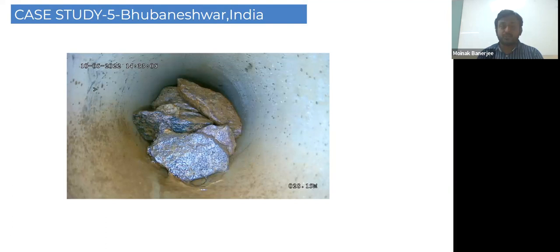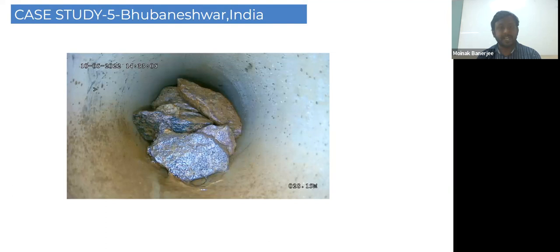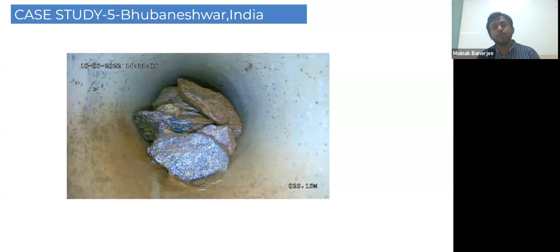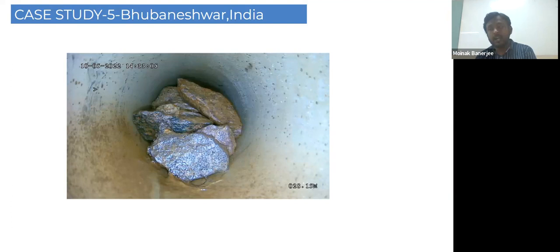Another case study is from Bhubaneswar, where the major problem is blockages. In this eastern city, pipelines have been fully blocked by stone accumulation, obstructing water flow and resulting in increased back pressure. The endo-90 robot was specifically used for finding those blockages — generally the network was in good condition, but unwanted particles were getting into the network, blocking and affecting flow rates in the pipelines.